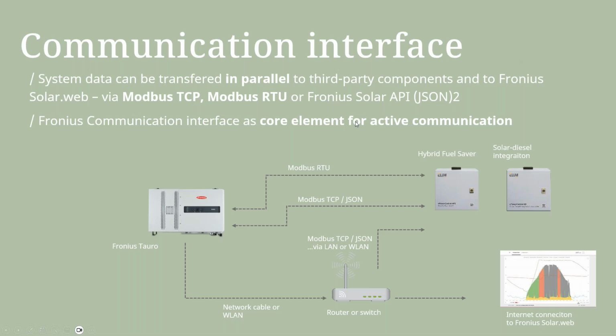So continuing with our presentation, as we can see, obviously this is the answer to our second Mentimeter question, which is the communication interface. The communication interface between the controller, in this example the Illum hybrid fuel saver controller, and the Fronius Tauro inverter is, of course, via Modbus. Modbus could either be Modbus RTU or Modbus TCP. It is also possible to communicate via the API using the JSON protocol. And then you can implement internet connectivity via wireless LAN or network cable.